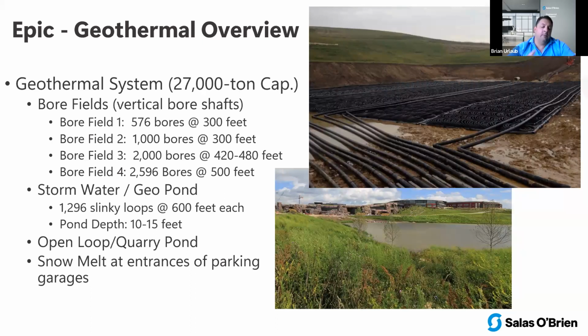And they started with vertical bore fields, and those are still being used today, primarily to maximize space, because they're doing other things over top of the bore fields. There's been a lot of research at this site - the University of Wisconsin-Madison has done a bunch of research about how this site is impacting ground temperatures, groundwater, where's the heat going, is it impacting water wells downstream underground. What they found after a lot of testing is that you get outside of any one of these vertical bores, 50 feet, 100 feet, and the temperature's back to the mean ground temperature, which is amazing.